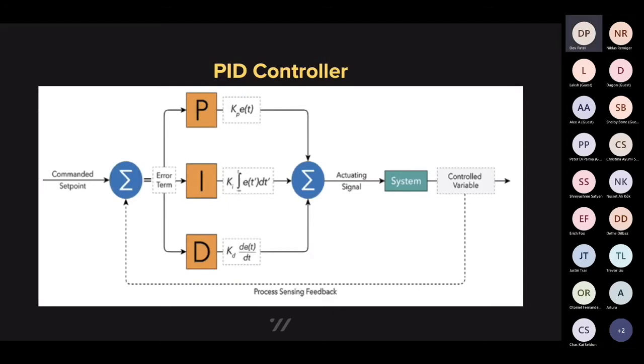Next, the PID controller. A PID controller, or proportional integral derivative controller, is a control loop using a feedback loop that continuously calculates an error term as the difference between the desired and measured values. The controller then applies a correction based on the proportional, integral, and derivative terms, hence the name PID controller. The controller has three parameters that must be tuned in order to achieve stability of the system: K sub P, K sub I, and K sub D. These are real coefficients corresponding to the error, the integral of the error, and the derivative of the error. The signal from the compensator is then the sum of the three terms.